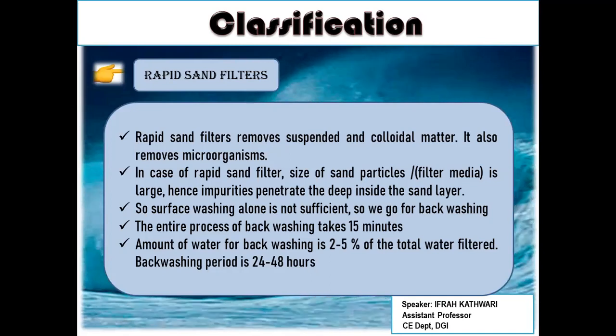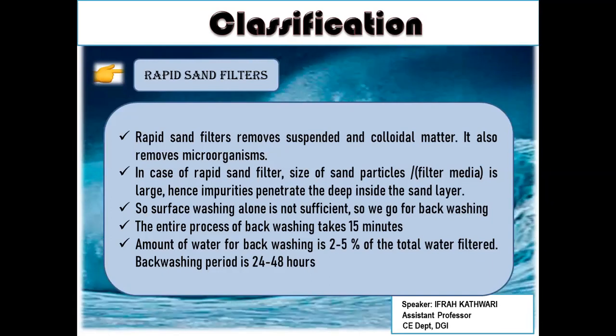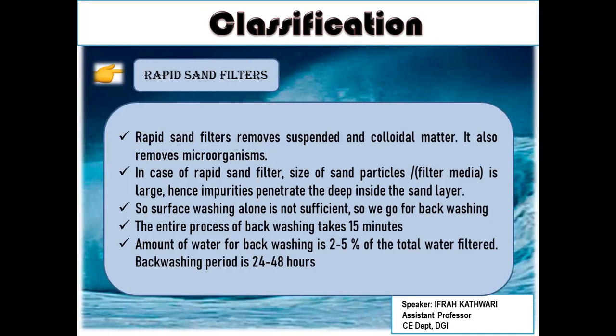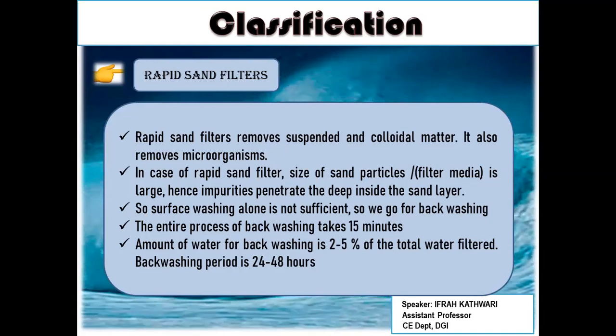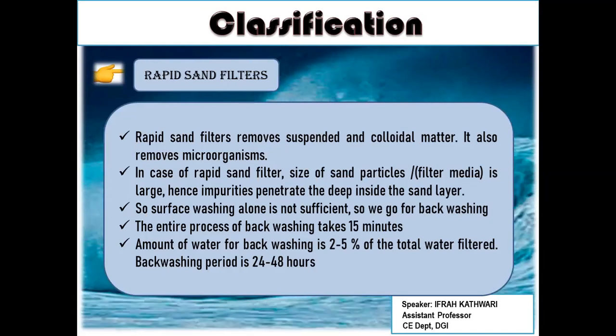Okay, the filters have coarser sand with a size of around 0.5 mm. The coarse sand is used as a filter media, as you all know. The water that is coming from the coagulation aided sedimentation tank is being filtered in these filters. These rapid sand filters are used for filtering the water which has been treated by coagulation aided sedimentation.